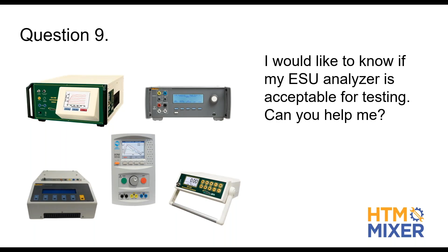So of all these generators, what worried me at the time is that if you're doing any calibration, you need a 1K, 2K, 3K, and a 5K — most analyzers don't have that. There are a couple out there that can do it, but not many. The other thing about BC Group is that they can handle both continuous and pulsed waveform — to my knowledge, the only one in the world that can do both. You might say, well, we only do continuous — but is that what you'll be doing two years from now? You don't know. That's why I mention it here.